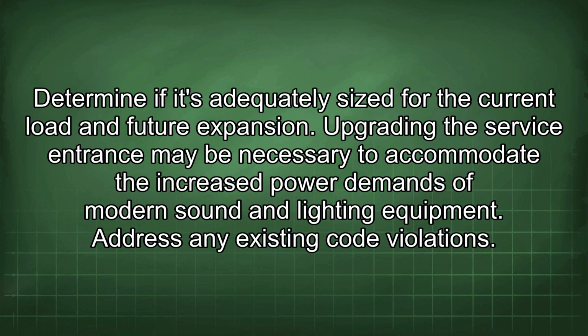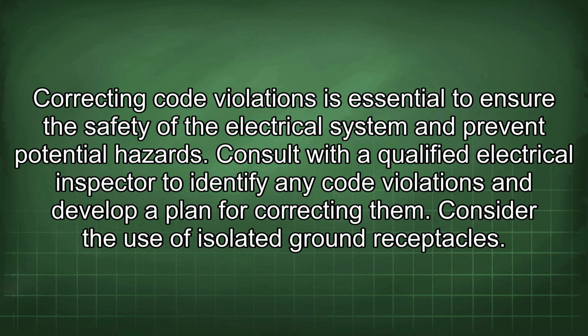Evaluate the existing service entrance. Determine if it's adequately sized for the current load and future expansion. Upgrading the service entrance may be necessary to accommodate the increased power demands of modern sound and lighting equipment. Address any existing code violations. Correcting code violations is essential to ensure the safety of the electrical system and prevent potential hazards. Consult with a qualified electrical inspector to identify any code violations and develop a plan for correcting them.